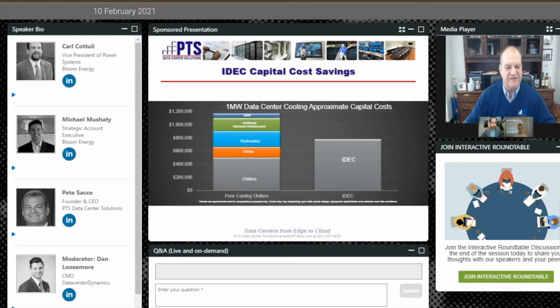On the left is the stack of buying and building chillers, CRAHs, hydraulics, pumps, all of your additional electrical infrastructure, and all of your BMS points, approaching $1.2 million for a megawatt install redundantly, as opposed to $800,000 — and by the way, they're building even more efficiently now.